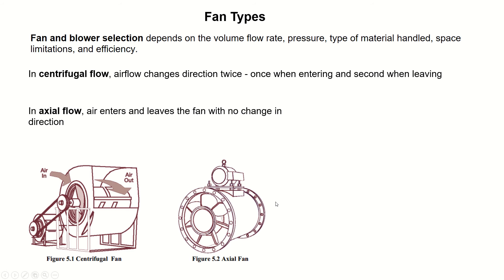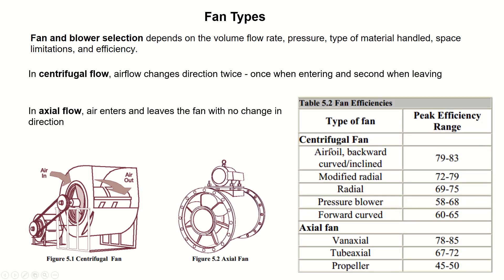This table shows fan efficiencies. The maximum efficiency for a centrifugal fan is for the airfoil backward curved type, which is 79% to 83%. The maximum efficiency for axial fans is also shown in the table.